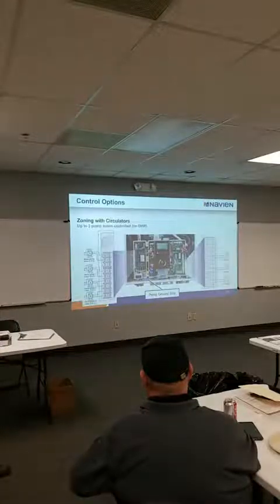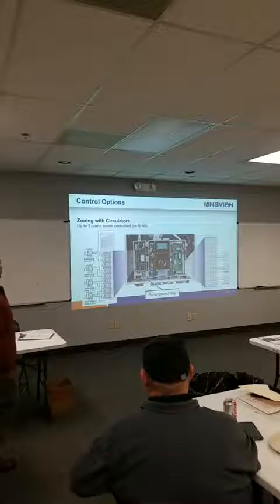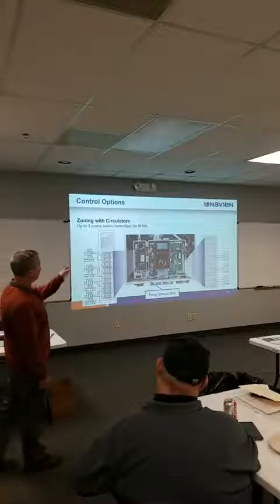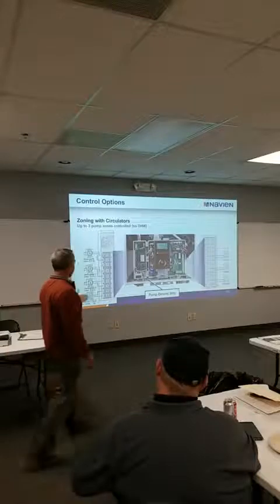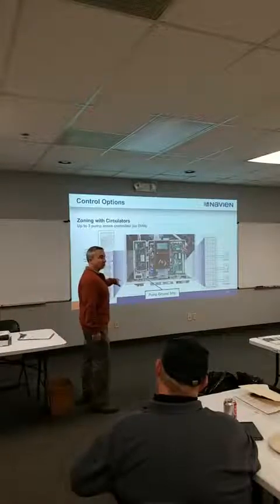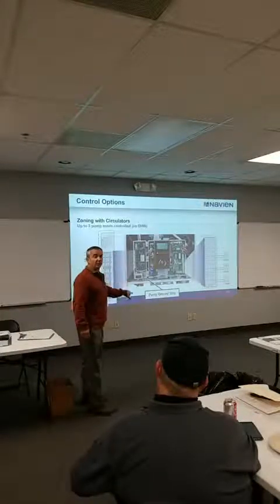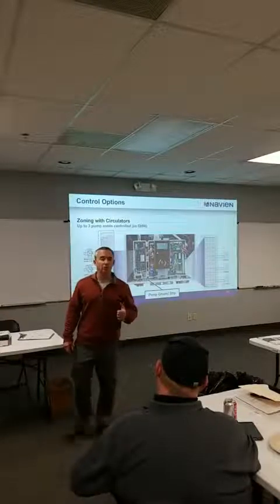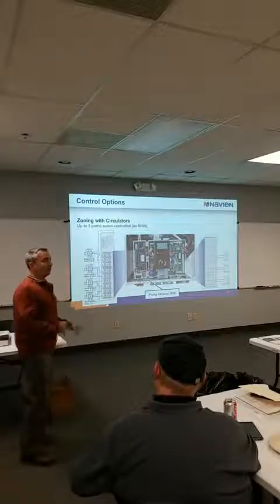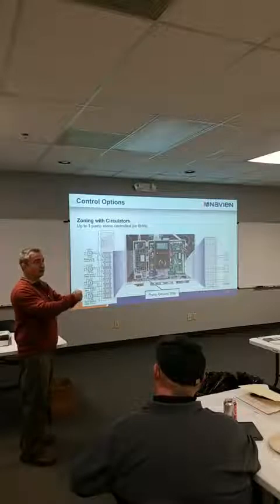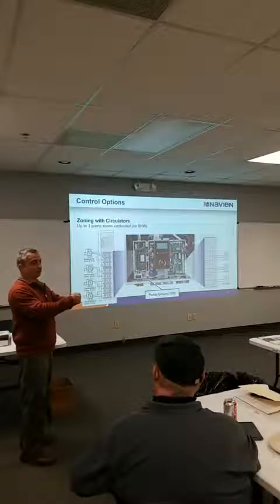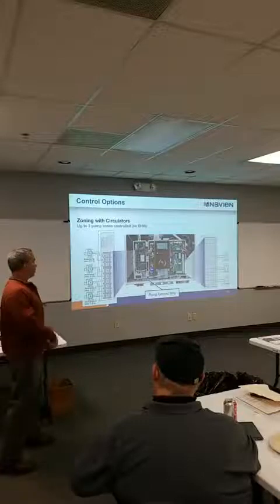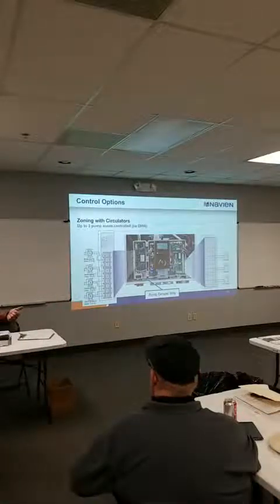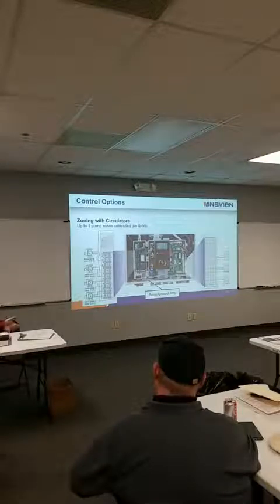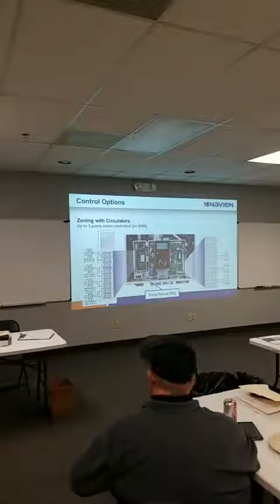So, there's just a breakdown. Again, this is in your manual. You'll see zone 1, thermostat 1, they kind of line up. We're also putting a pump grounding strip on this board, which we didn't have in the NHB. So if you wanted to ground out your boiler pump and your system pump, you had to wire to the back of the unit, which is a real pain, because you can't get back there. You know, you got a long screwdriver, you got wire tie, or you can cut a ground wire up front and try to do it that way. But the pump grounding strip is nice. It's something we had asked for and they put it in, so.